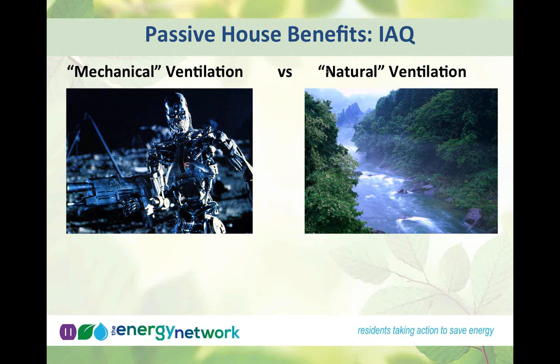This is a centralized heat recovery system in a passive house. The heat recovery ventilator brings fresh air in, typically filtered, from a good location, passes it through the unit, and delivers it to the living spaces. At the same time, the bathrooms, kitchens and laundry areas have their air extracted and sent through the heat recovery ventilator, where it doesn't mix with the incoming fresh air but warms it, and that air gets sent out of the building. This runs all the time, so unless the weather's nice and you have windows open, it gives you a reliable and consistent source of fresh air 24/7. By contrast, in a typical building, this chart shows various sources of leakage.